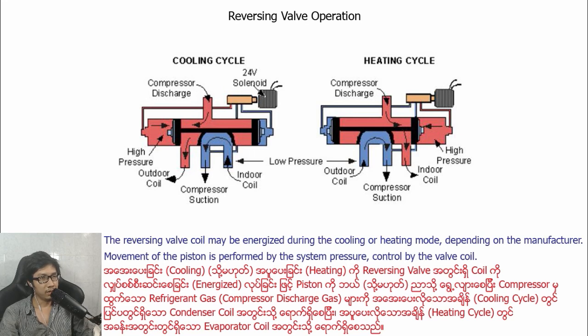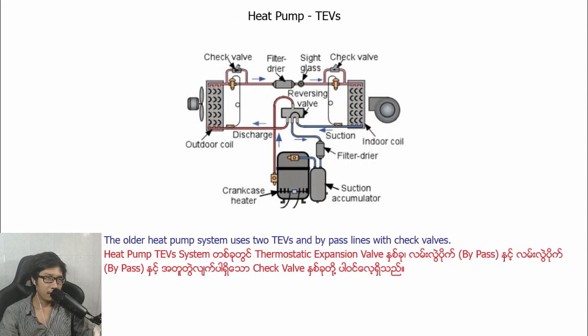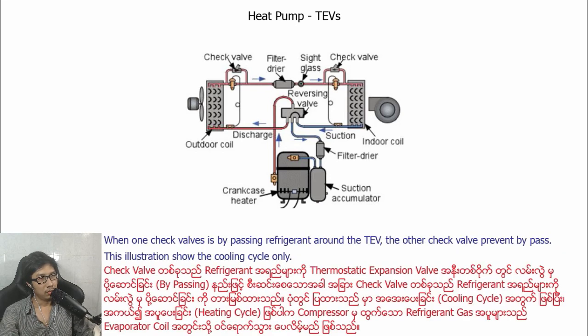Movement of the piston is performed by the system pressure controlled by the valve coil. Heat pump thermostatic expansion valve (TEV). The older heat pump system used two thermostatic expansion valves (TEV) and a bypass line with a check valve. One check valve is bypassing refrigerant around the TEV. The other check valve prevents bypass. This illustration shows the cooling cycle only.